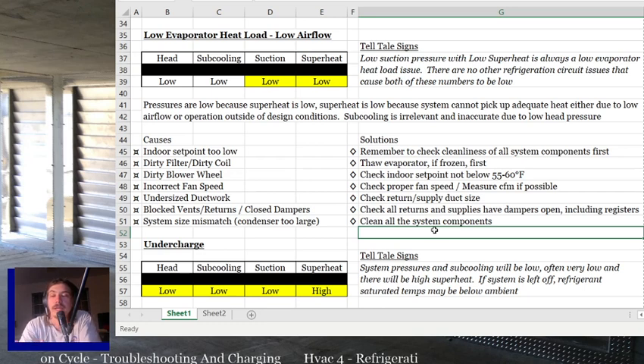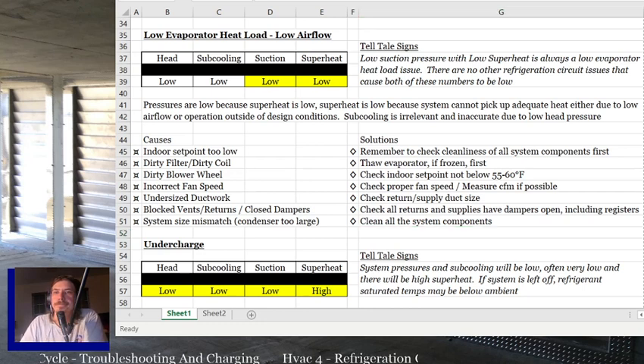I will tell you, if that happens, 9 times out of 10, it's going to be a dirty coil. It's usually what it's going to be. That's what you should do, clean the coil. That doesn't mean it's always what it is, though. You need to know the other things it could be. Does that make sense? Does that help you out? All right. Any other questions on low evaporator heat load?